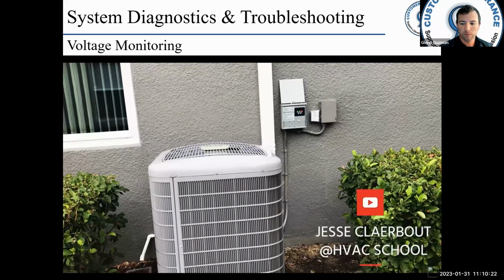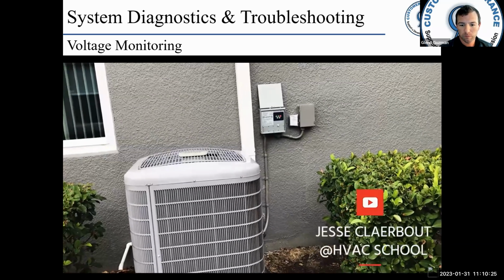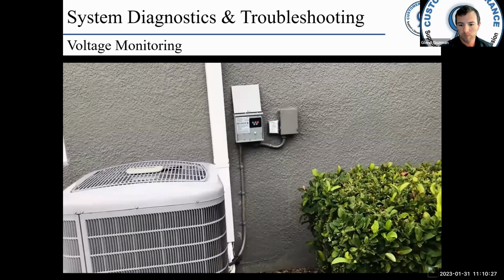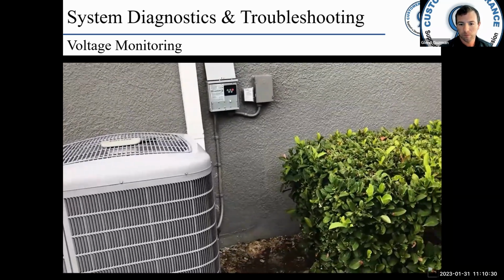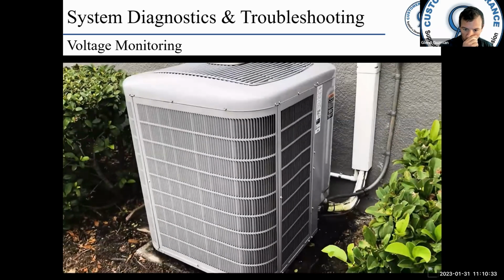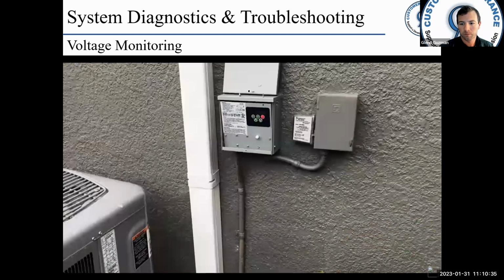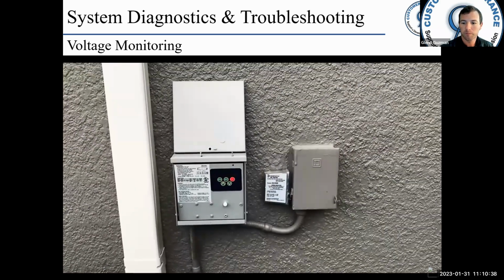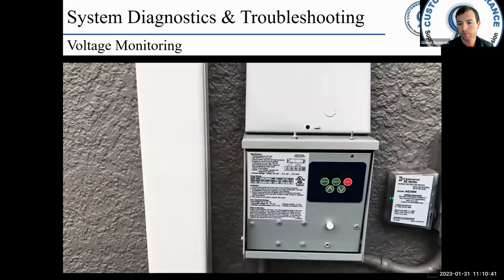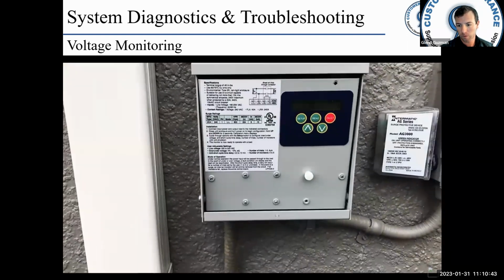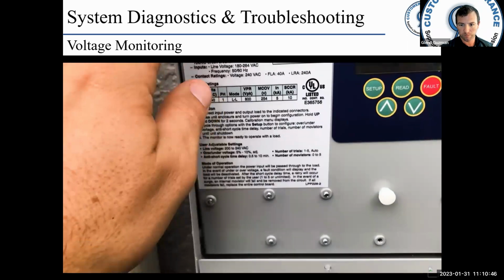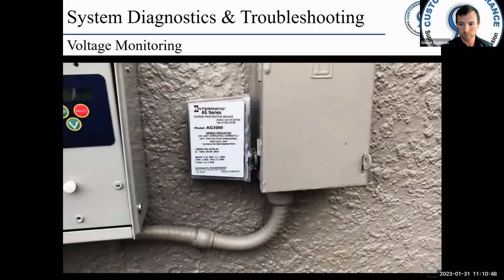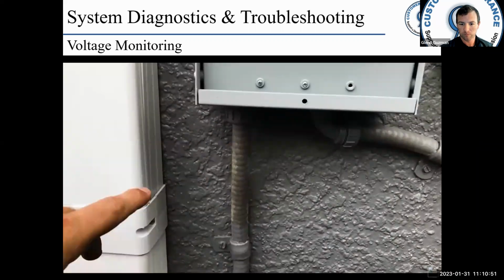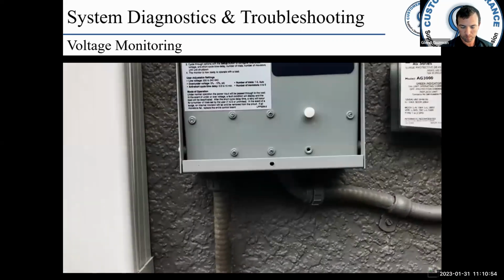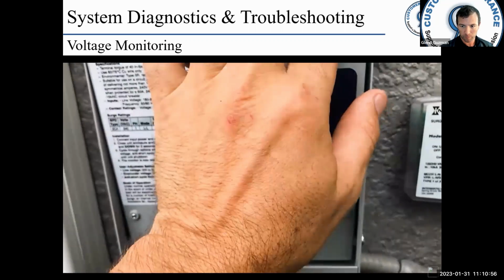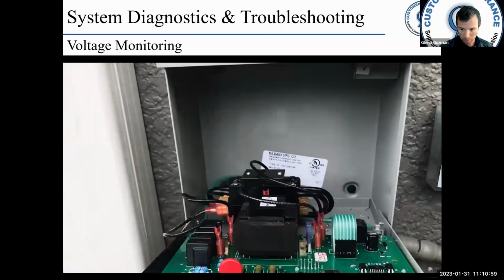Okay, today we're going to go over how to properly install an ICM 493 single phase voltage monitor with surge protection. We're doing these on all of our Infinity systems that have inverter boards. On this particular one, we have our service disconnect on the right hand side, and then we have our ICM 493 here. So first off, we're going to want to come out of the disconnect into our voltage monitor surge protector here. On the back side of this, I'll show you how it's actually wired up.